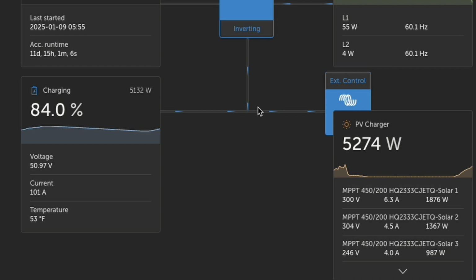Now, as we're looking at this, I want to point out that over here this says external control. What this means is that this charge controller, which is a SmartSolar 450/200, a pretty significant charge controller, is responding to some sort of external source. In this case, that external source is the Pylontech Master US5000 BMS passing information on to the Cerbo GX, and via DVCC, Distributed Voltage Current Control, which we'll look at in a minute, it is controlling exactly what is happening out of this charge controller. As the system charges and discharges, that's going to be changing voltage limits, charge current limits, etc. But this is a pretty good indication that you're working with a system that has sophisticated battery communications.